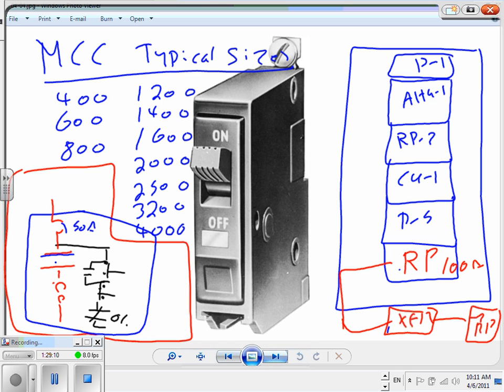And even receptacles and lights, Eric, my friend, with a multi-wire branch circuit right now, they have to either be a 3-pole circuit breaker, one big circuit breaker, or 3 circuit breakers tied together with an approved handle. If it's a multi-wire branch circuit, which you should use multi-wire, that's to save a lot of money. So a standalone circuit breaker, it's becoming so hard to find one because you're always using multi-wire branch circuit tying the 3 together.